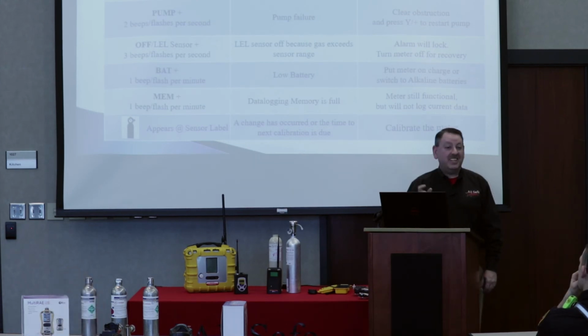If you ever look down and you see the LEL sensor says off, that means the sensor reached 100% of the LEL, the lower explosive limit, and the sensor shut itself down. So it won't burn out and so it won't be a cause of ignition. Okay? So if you ever look down and you see that, that's a very dangerous situation. Back out of that space as quickly as you can.